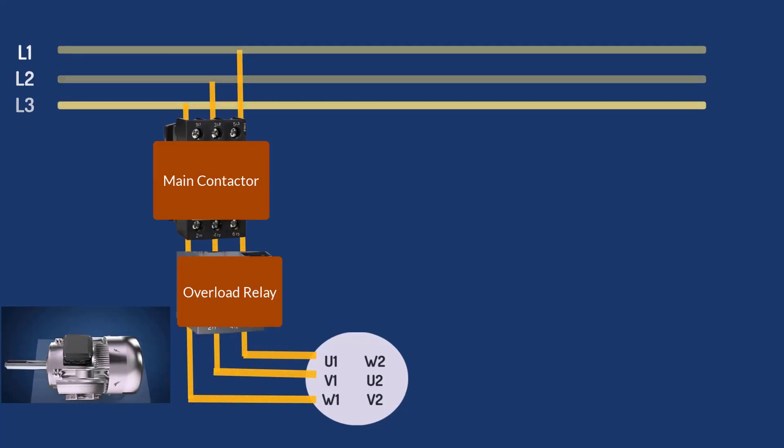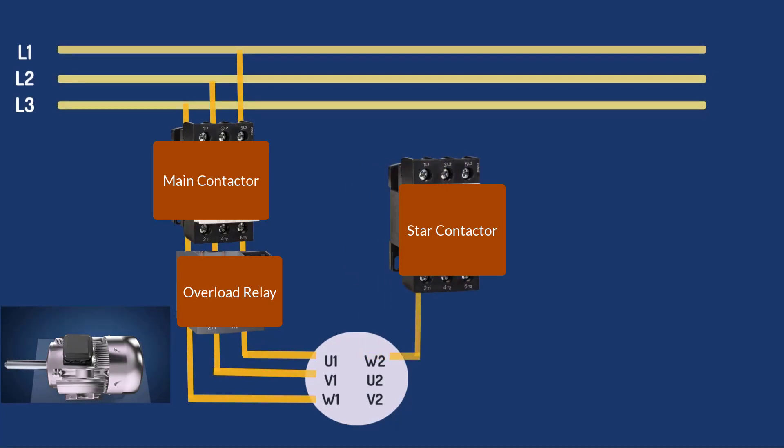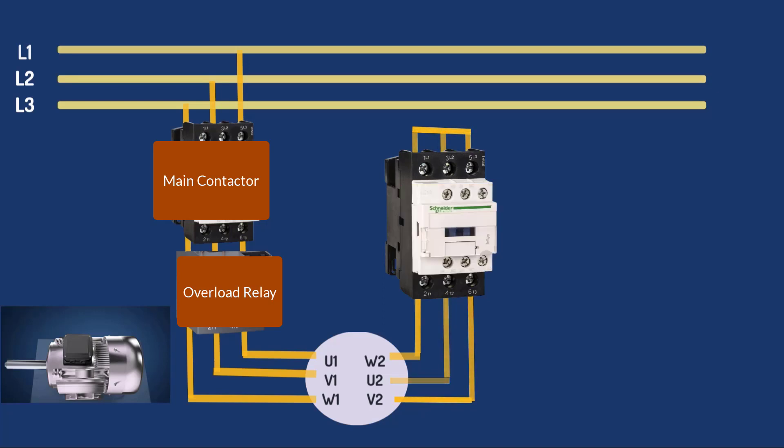Let's understand the star connection. For star motor winding connection, we can add another contactor named star contactor and connect it to W2, U2, V2 terminals of the motor. We will short the other end of the contactor like this. The current in star state is one-third of the current in delta state, hence the contactor rating is one-third of the motor rated current.